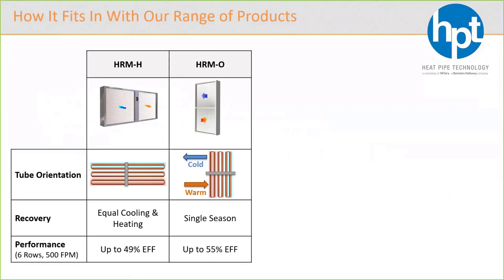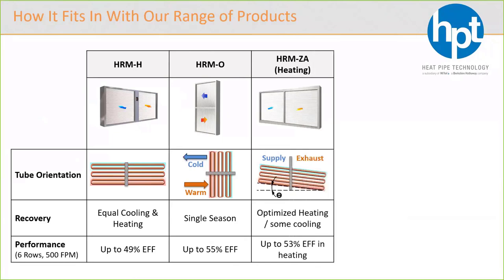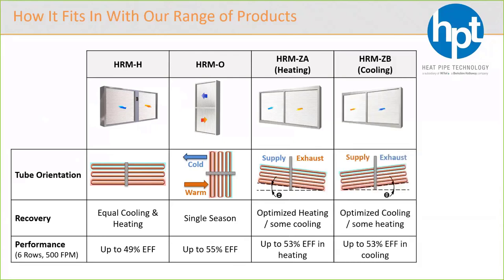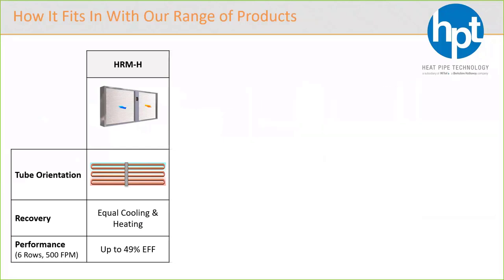There's also a product we came up with recently, which is the HRMZ, and it's optimized, hence the Z, for one season. In this case, it's optimized for heating, which would apply to most of North America. But there's also a B, which is optimized for cooling, and that could be used in Southern Florida, out in Phoenix, Arizona, those sorts of places. What we're doing is we're using a little bit of tilt to use gravity to help us get better performance. However, we have special circuiting, so you still get some recovery on the off season. Now, we're going to just look at the equal cooling and heating. So just zoom in on the HRMH.